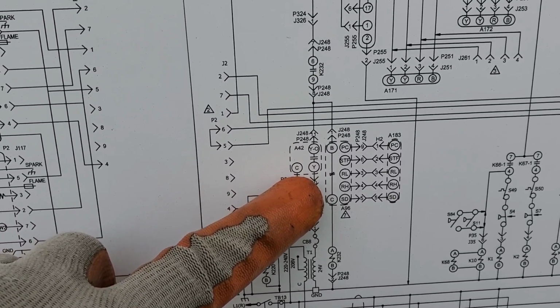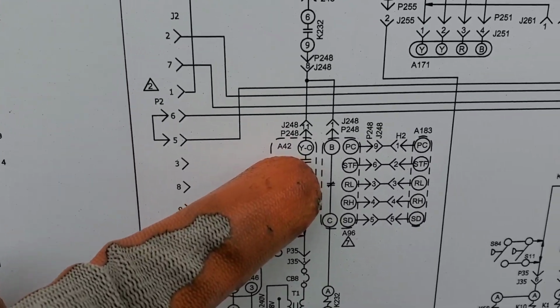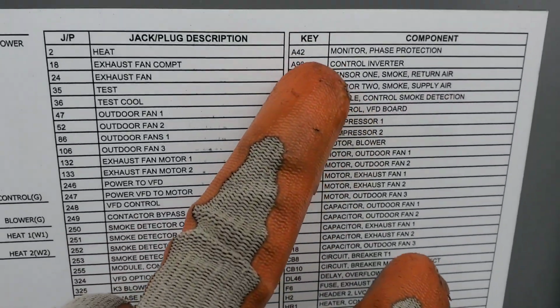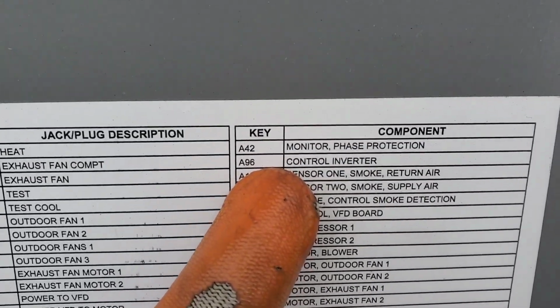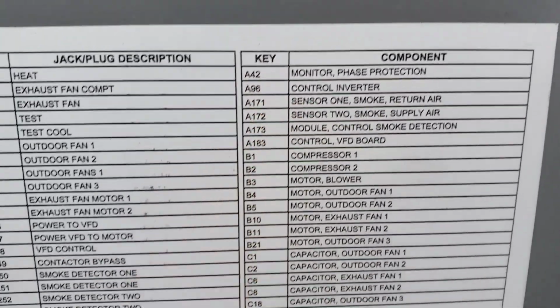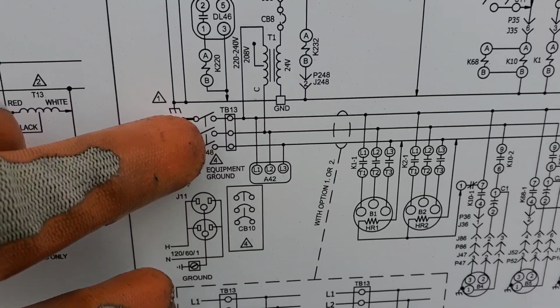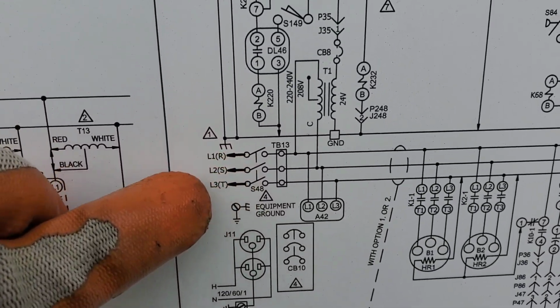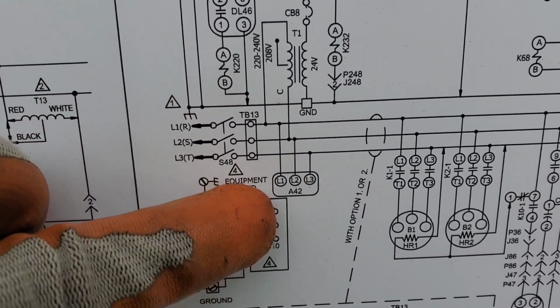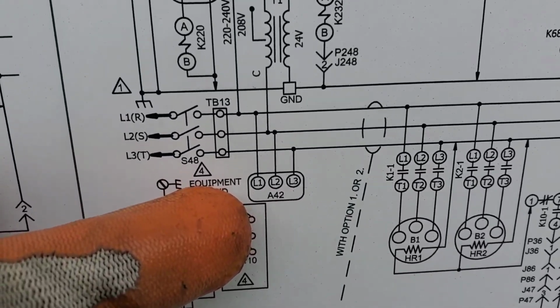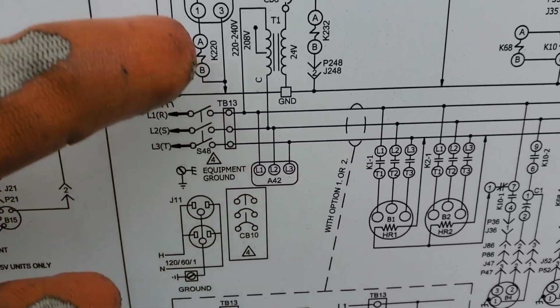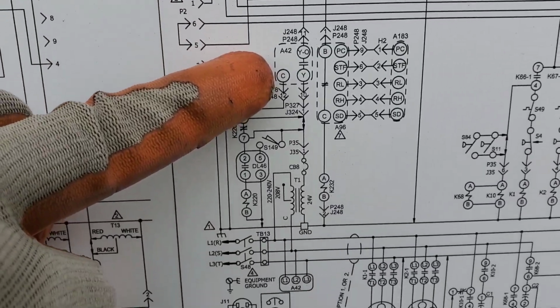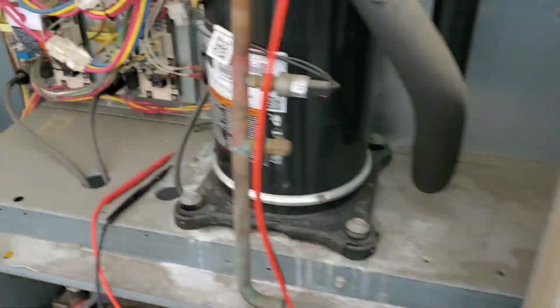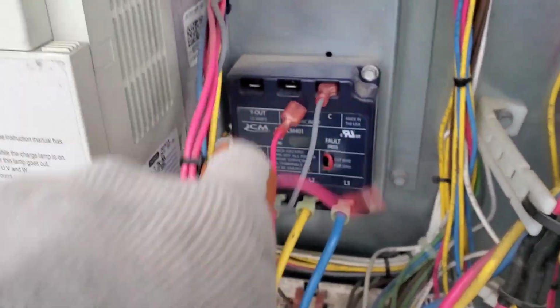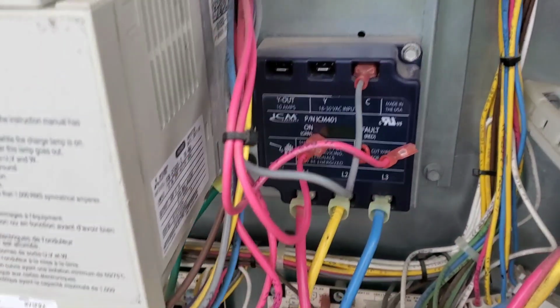So what is this device? It is A42, and on the list A42 is monitor phase protection, and this is also connected to the main incoming 3-phase supply here. If you can see line 1, line 2, line 3, A42. Okay, so physically I pulled out these wires just to check. Okay, so this is the phase monitor.